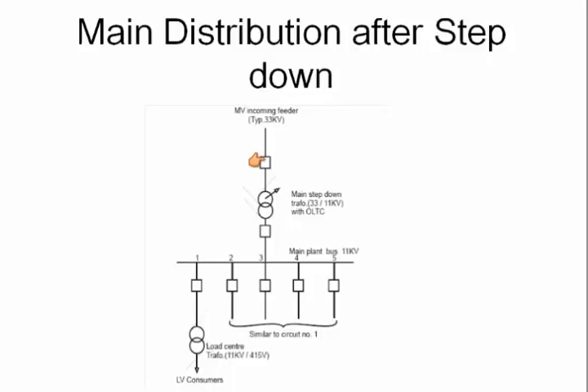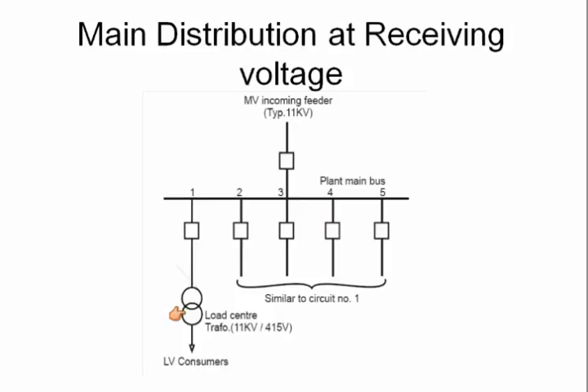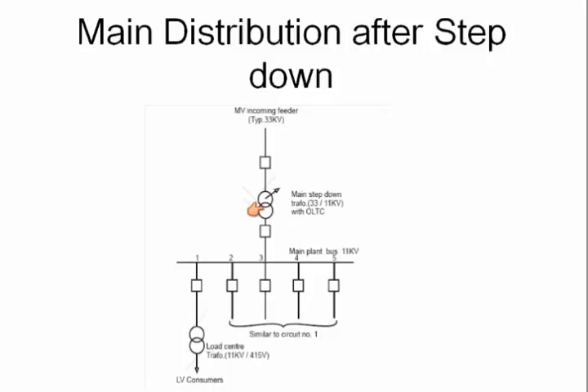This symbol is for an on-load tap changer. This arrow, on-load, means you can change the tap on-load when the transformer is on. While here, it's an off-load tap changer. You need to turn off the transformer to change the taps to regulate the voltage. Here, it's done when the transformer is on. So that's the symbol, arrow. For lower voltage, you have a transformer with an off-load tap changer. You have loads that can run at 11 kV.